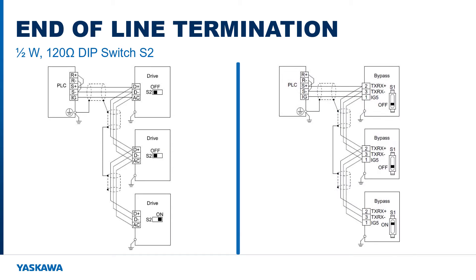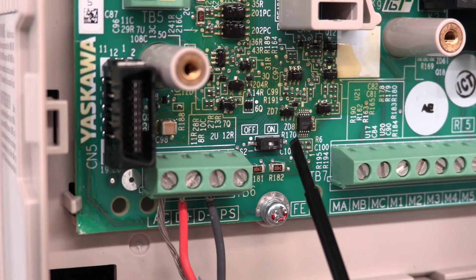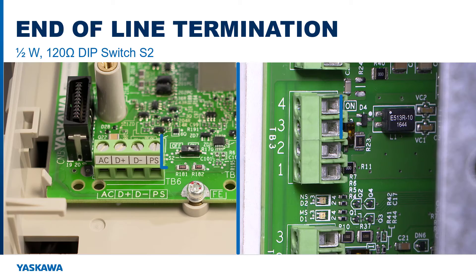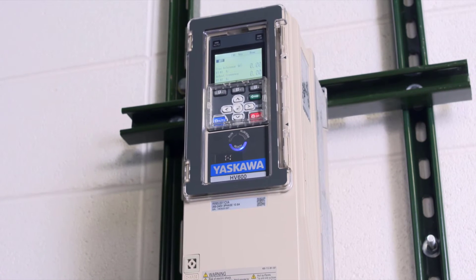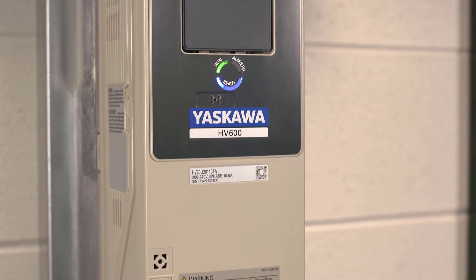Before completion, identify if this is the last device on the network. Enable the termination resistor only when the device is at the end of the communication network. Set DIP switch S2 to the ON position to enable the termination resistor, or add the correct external resistor across the communication terminals.